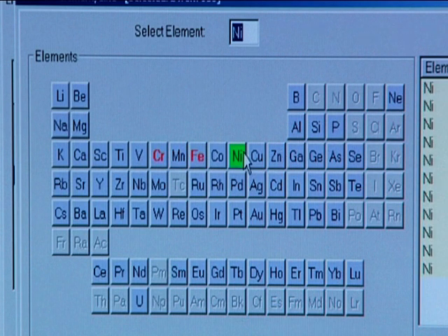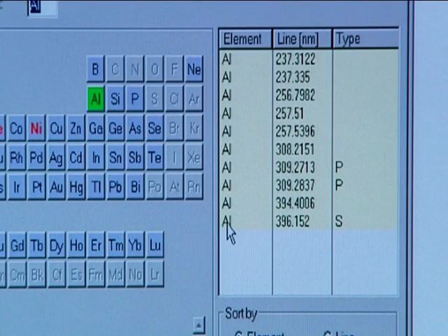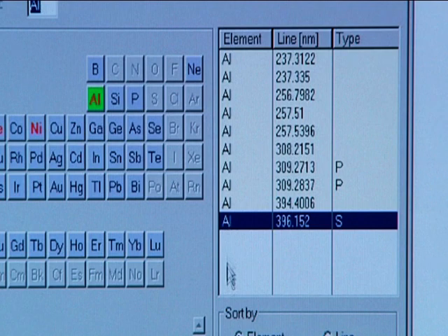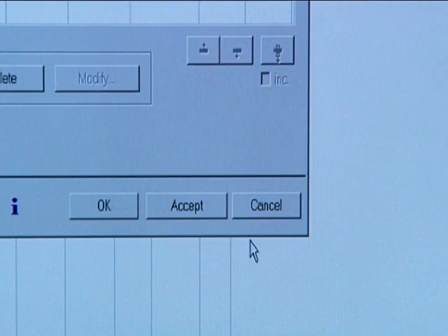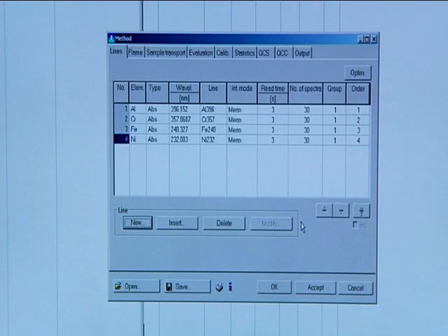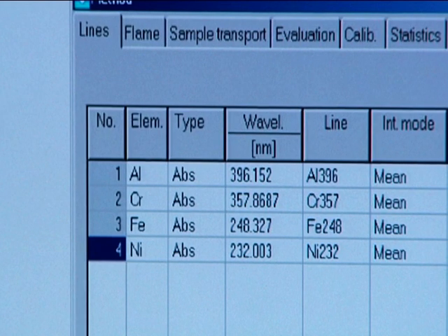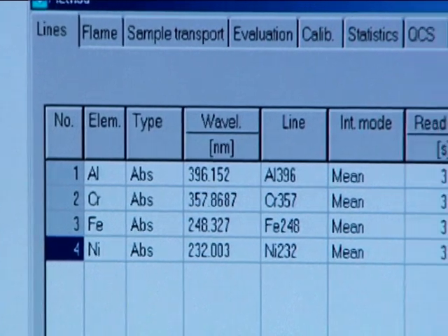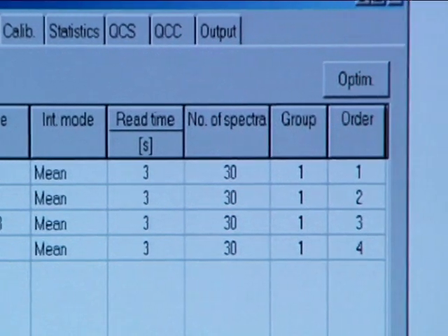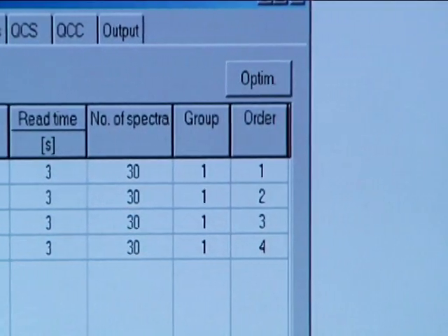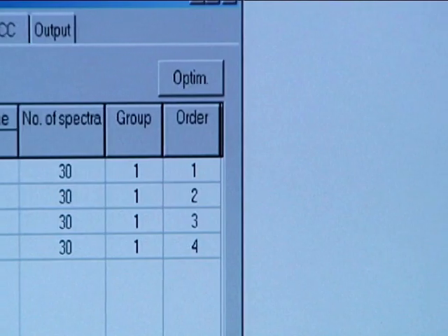In contrast to classical AAS, the software of the ContraAA is distinguished by being directed to multi-element measurements. Due to the standard parameters contained for all techniques and elements, and the automated optimizing routines, multi-element methods can be developed in a very short time. As a result of the improved, easily surveyed arrangement, the extent of the functions can be mastered intuitively. A context-sensitive help function gives answers to all the questions which may arise when operating the software.